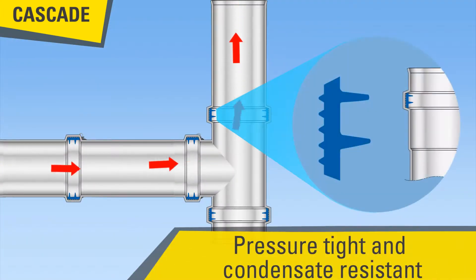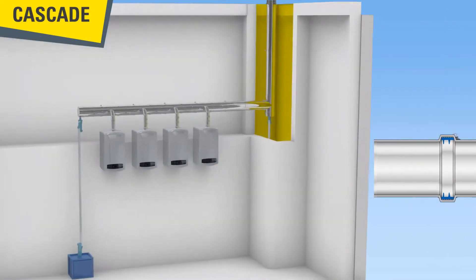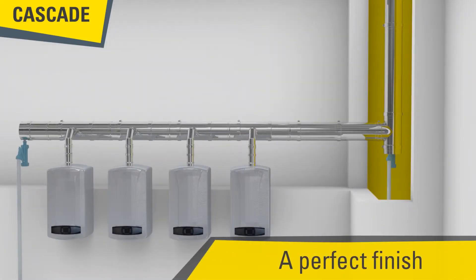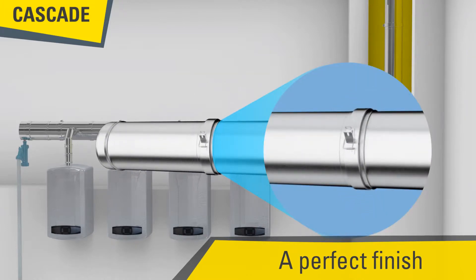The perfect pressure tightness — less than 200 Pascals — and condensate resistance is secured with a silicone seal rated to temperatures less than 200 degrees Celsius. The Poujoulat chimney flues are recognized by professionals for their design adapted to easy installation.